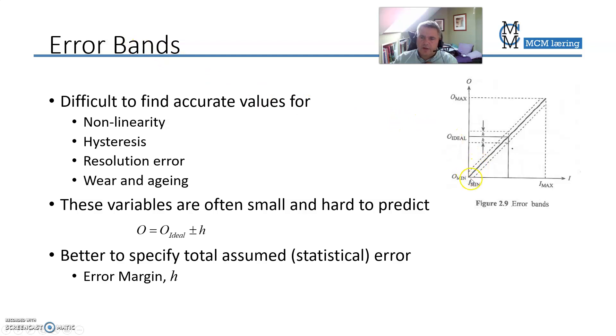So you say that the output should follow this line, the whole line here, but your true output-input relation is somewhere between the two dotted lines. So the distance between the dotted lines is called the error band. So you have the true relation here as a filled line and then the error band, which is up and down from there.